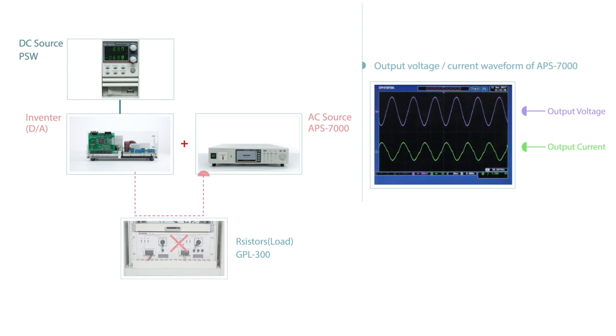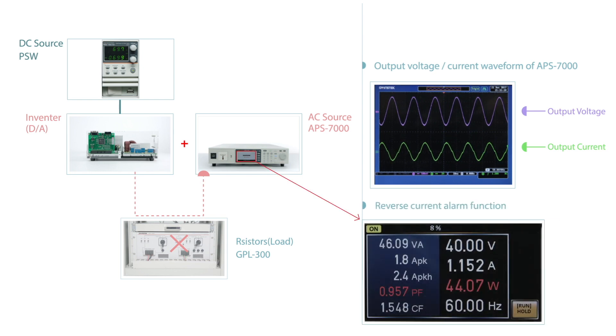When removing the load instantly, the APS-7000 will directly receive the current from inverters. The APS-7000 switches the output current to current sink and the phase between voltage and current changes from 0 degrees to 180 degrees. The APS-7000 can help users to evaluate the output characteristics of the inverter through red numeric readings.